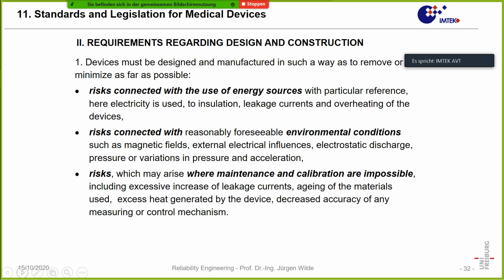Sometimes not only inputs are calibrated, but also outputs can be calibrated. That means it is not possible, so the devices must be stable over time, and their input and output must not change, for instance, just according to aging or such a thing. Also, you cannot repair an implanted device.